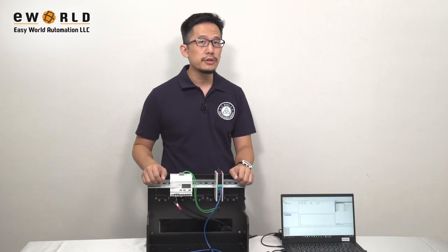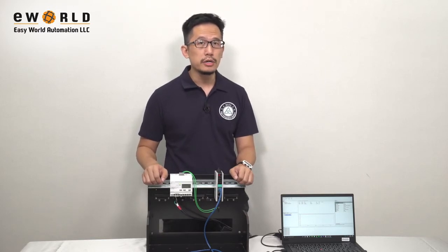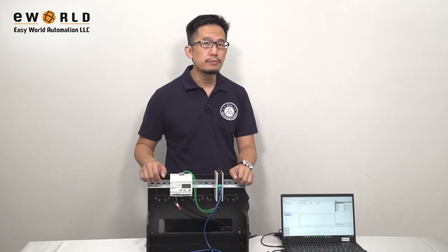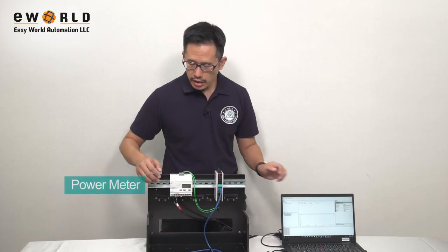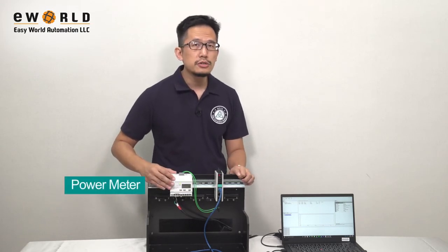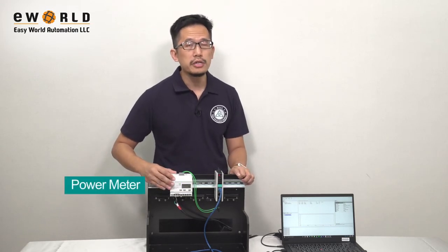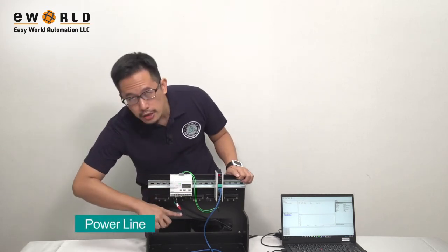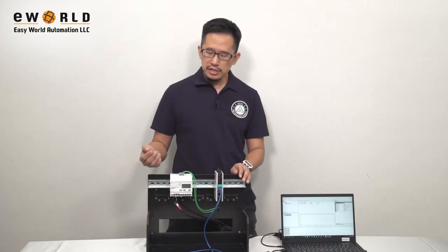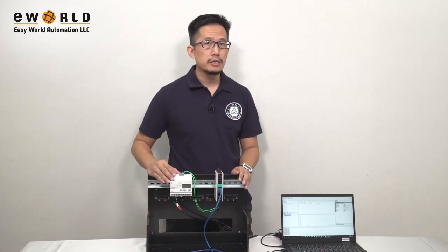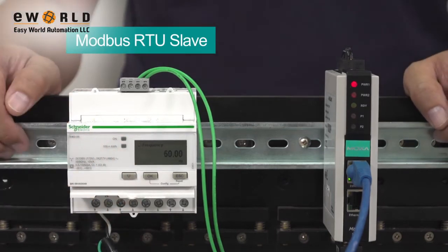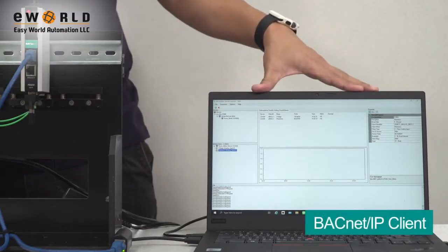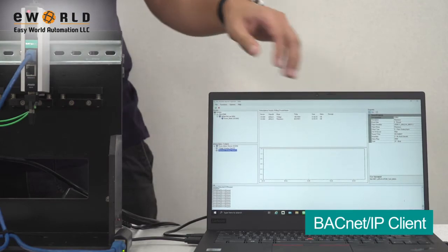Integrating Modbus devices into your BACnet IP network can be a challenge due to the different protocols involved. Here we have a BACnet IP client simulator running on this PC, and we have a power meter that measures the usage and the quality of the power coming through this power line. To connect this power meter to our BACnet IP network, we have to convert Modbus RTU protocol, which the power meter uses, to BACnet IP protocol, which our BACnet IP client uses.